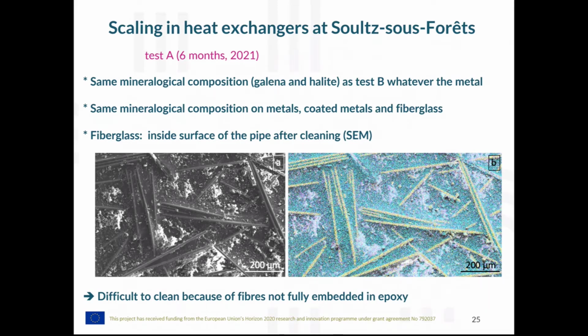As regards the fiberglass, I had a look at the inside surface of the pipe after cleaning with scanning electron microscopy. On the left side of the figure, you can see the fiberglass as the internal part of the tube. What appears white is the deposit, which has not been fully cleaned. When we look at the right part of the figure, in yellow are the glass fibers. This is silica, which appears.